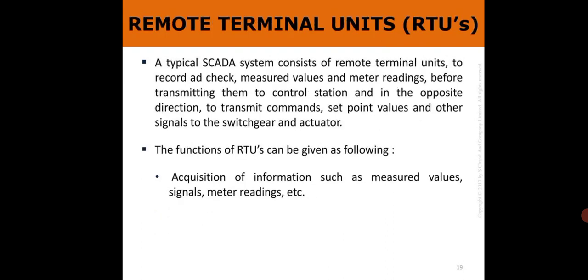Next is remote terminal units, RTU. In previous lectures we have studied the RTU in detail. So in this, a typical SCADA system consists of a remote terminal unit to record, check, measure values and meter readings before transmitting them to a control station and, in the opposite direction, to transmit commands, set point values and other signals to the switchgear and actuator.